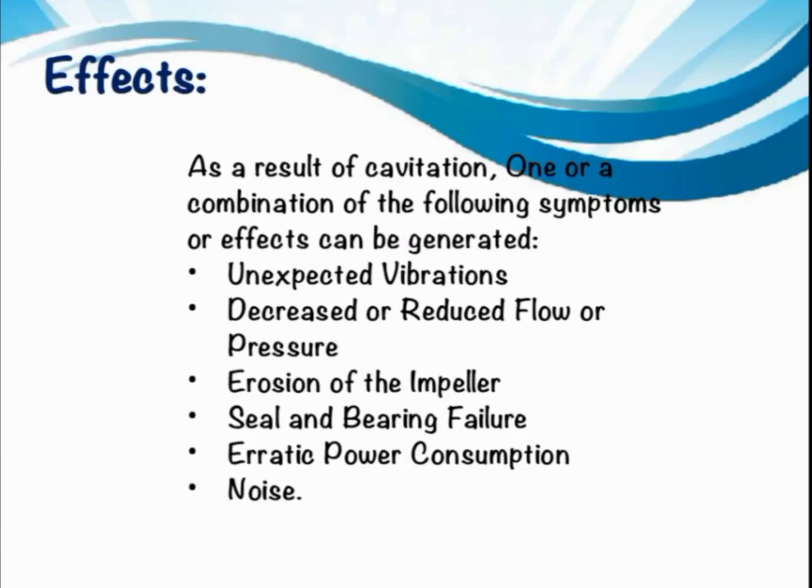Effects of cavitation. As a result of cavitation, one or a combination of the following symptoms or effects can be generated. First, unexpected vibration. Second, decreased or reduced flow or pressure. Third, erosion of the impeller. Fourth, seal and bearing failure. Fifth, erratic power consumption. Sixth, noise.